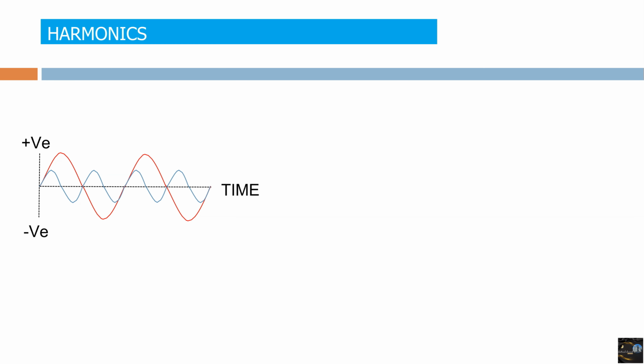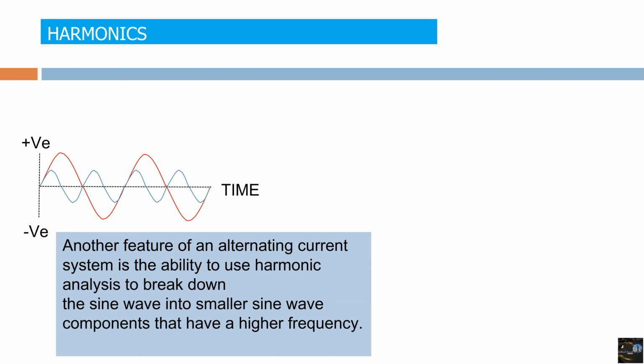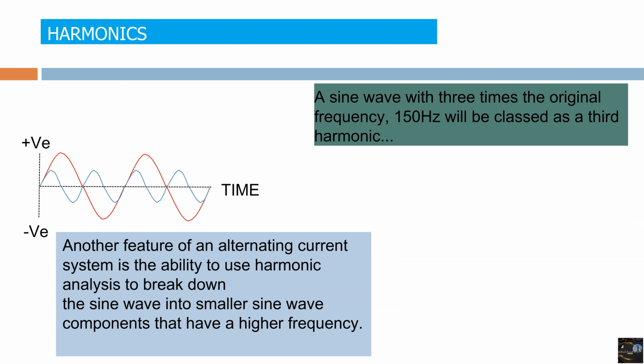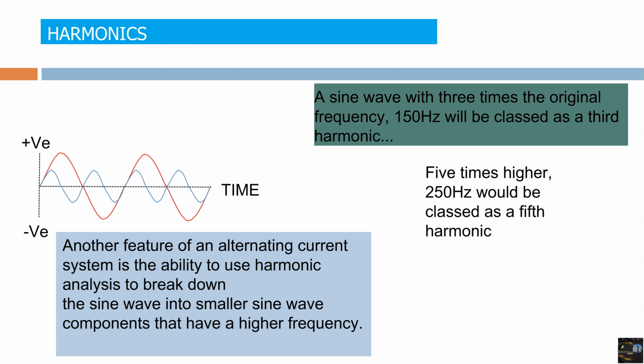Another feature of an alternating current system is the ability to use harmonic analysis to break down the sine wave into smaller sine wave components that have a higher frequency. A sine wave with 3 times the original frequency, for example 50 multiplied by 3 is equal to 150 Hz, will be classified as a third harmonic. Similarly, 5 times higher, for example 50 multiplied by 5 is equal to 250 Hz, would be classified as a fifth harmonic. And similarly, we have the seventh harmonic.